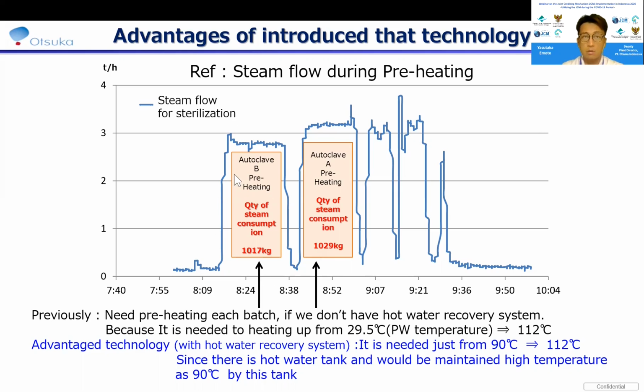I mentioned autoclave B and autoclave A as preheating here. Why do I call it preheating? Because this machine has to heat up to prepare hot water before starting production; we often call this process preheating. As I mentioned, previously, if we don't have a hot water recovery system, it is needed to heat up from 29.5 degrees until 112 degrees.